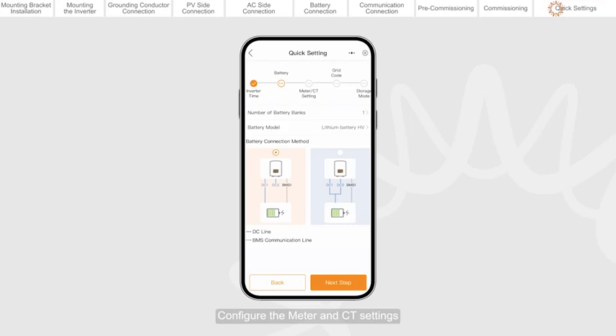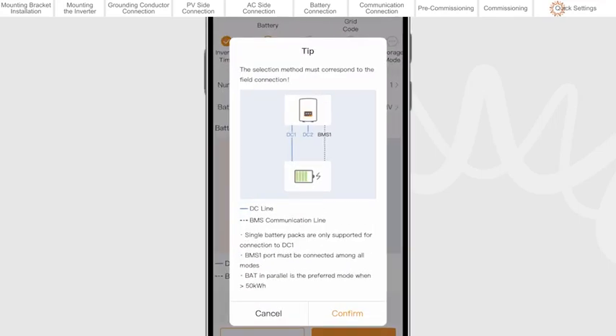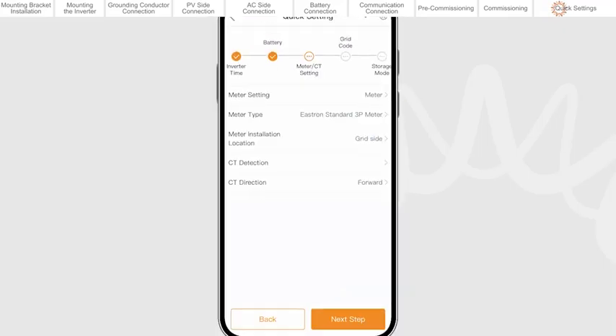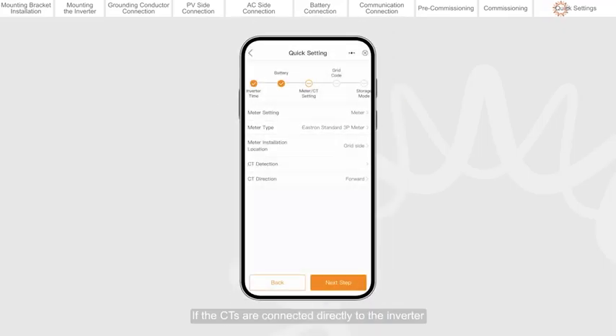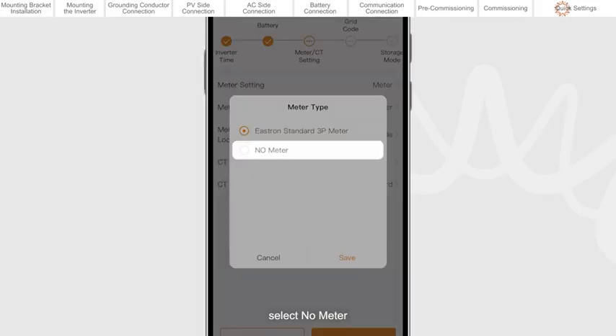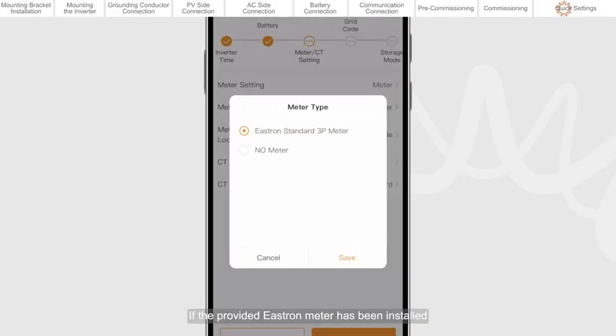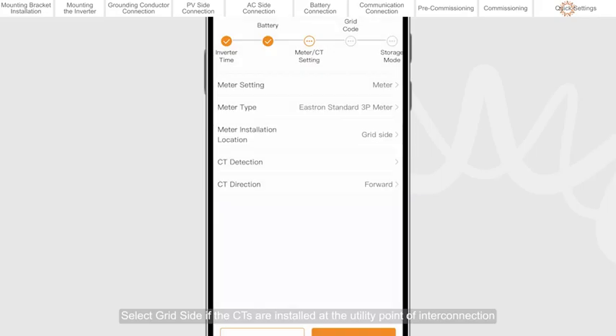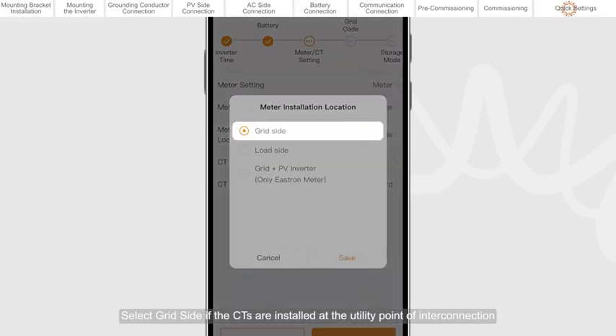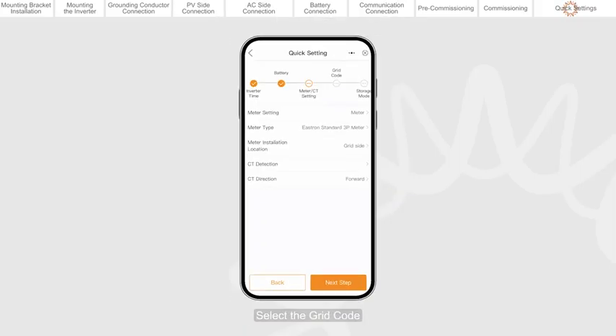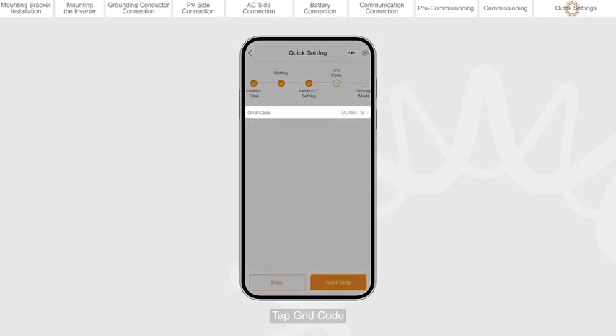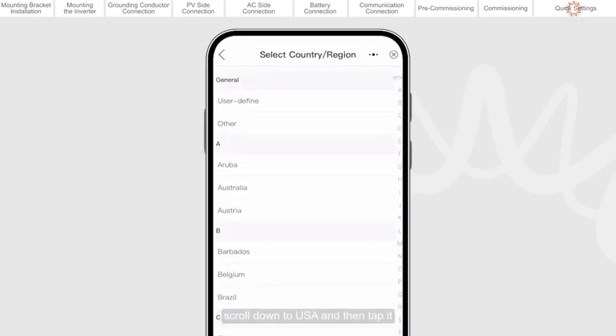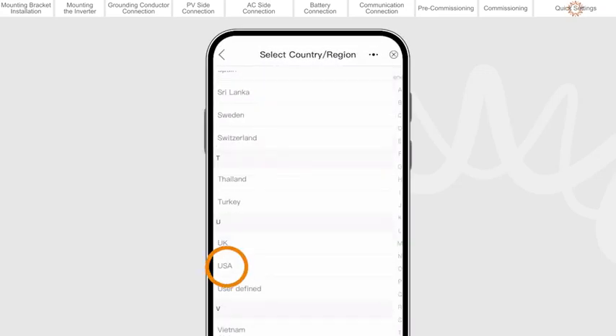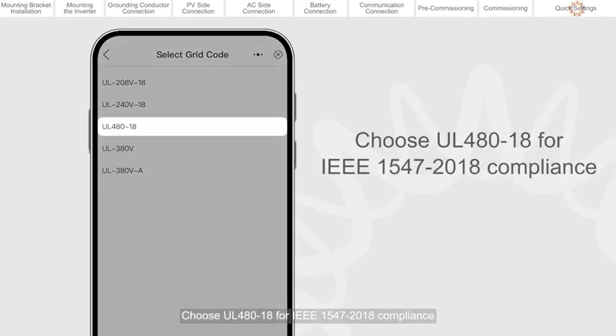Configure the meter and CT settings. If the CTs are connected directly to the inverter, select No Meter. If the provided Eastron meter has been installed, select Eastron 3P meter. Select Grid Side if the CTs are installed at the utility point of interconnection. Select the grid code. Tap Grid Code. Scroll down to USA, and then tap it. Choose UL480-18 for IEEE 1547-2018 compliance.